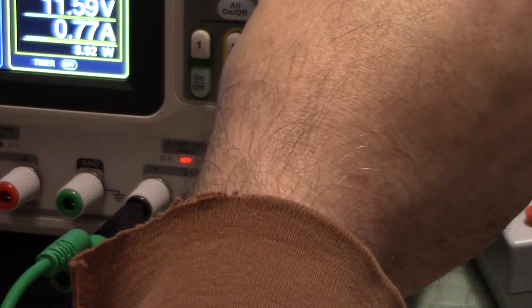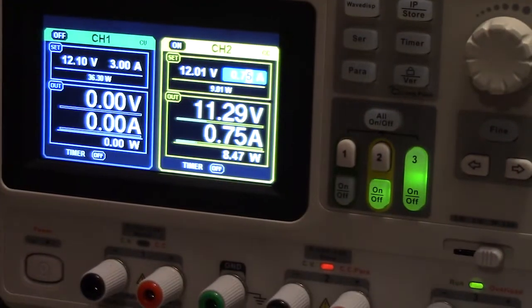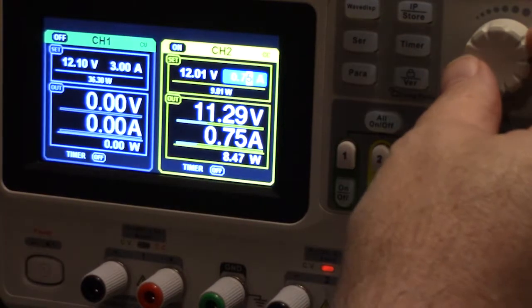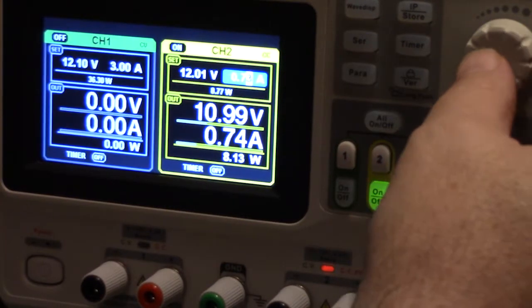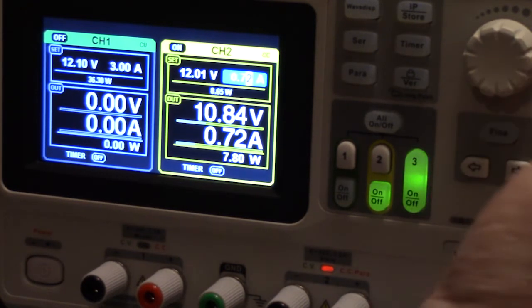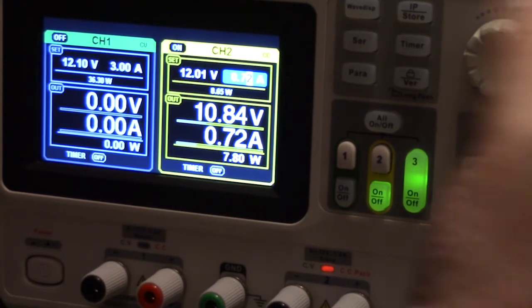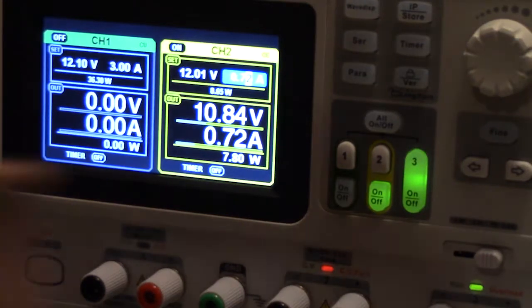I always thought these things are supposed to shut off if you get beyond this. This doesn't shut off, this just degrades the voltage. See the voltage coming down as I'm reducing the current limit. It's reducing the voltage to drop the current. I'm usually used to these things shutting off when they hit the current limit, but as long as it's limiting the current that's fine, that's acceptable.